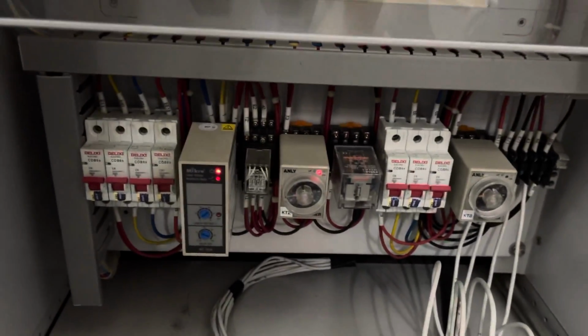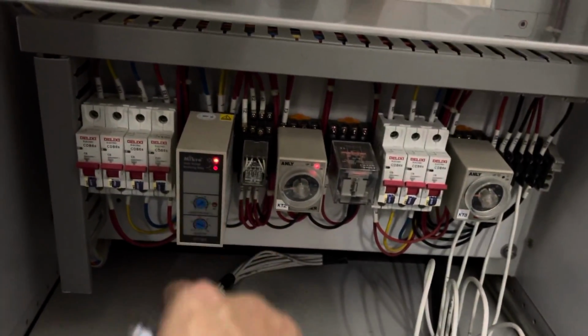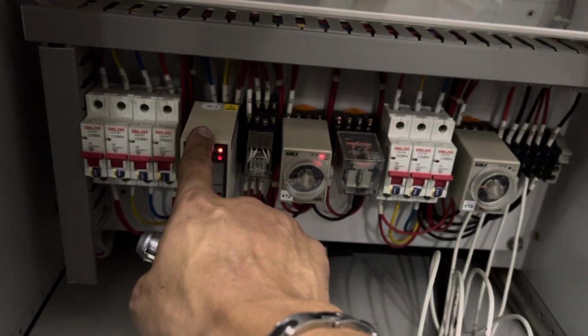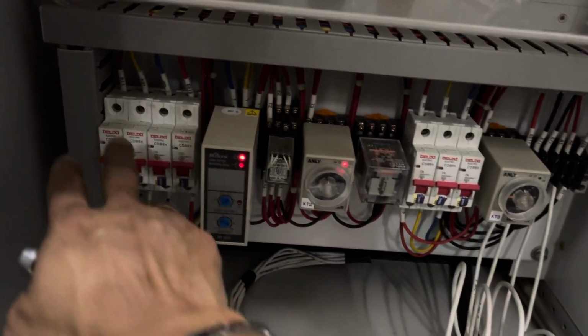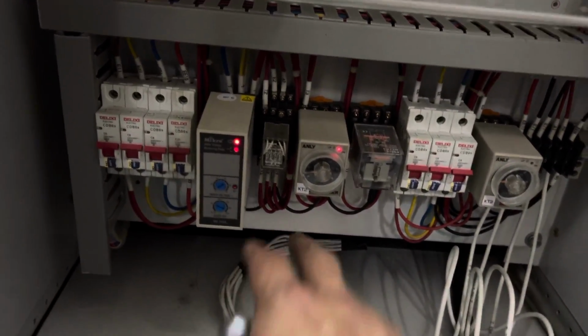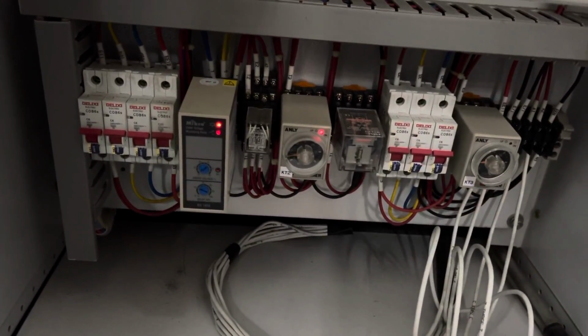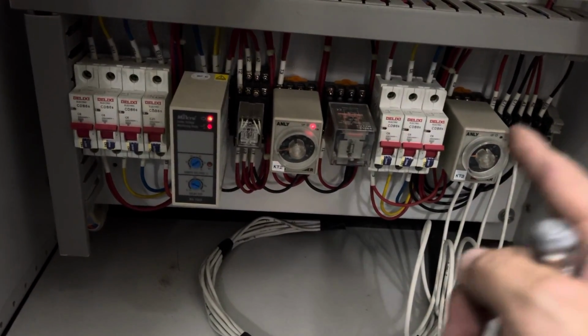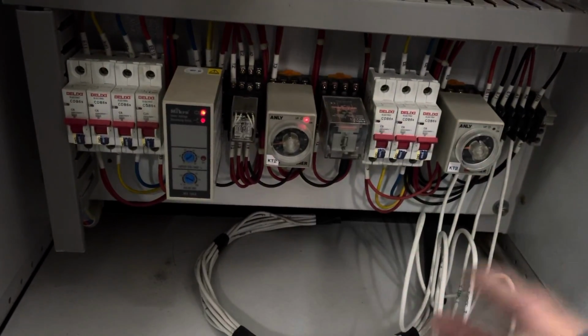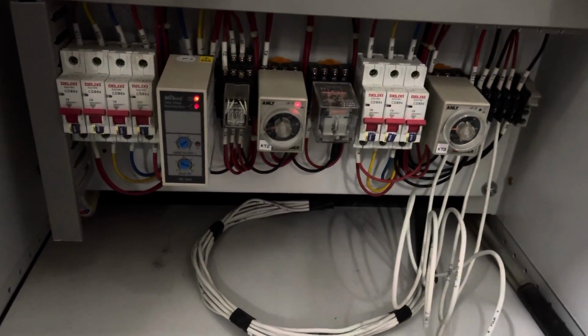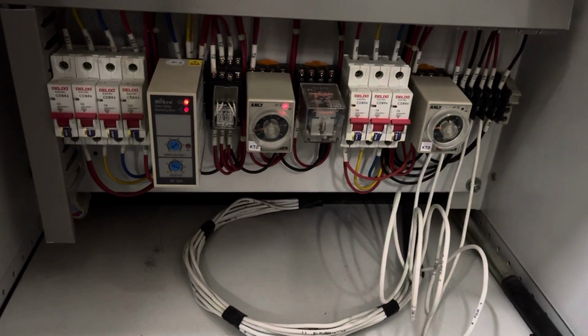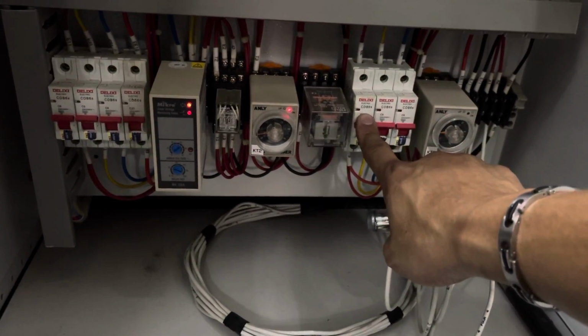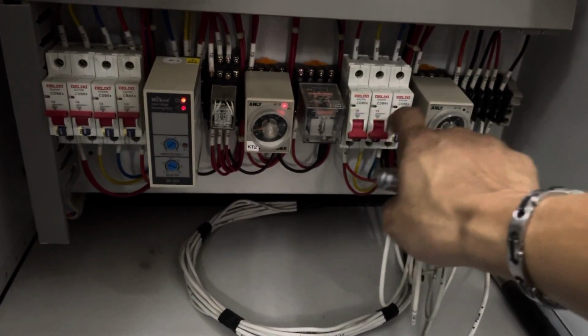Okay, what we are going to do here, we are going to trigger this UVR relay by switching off the control MCB here, then allow the signal to call the genset to start automatically, and then afterwards, we're going to normalize back and allow the genset to stop automatically. Okay, first step, off the genset MCB first.